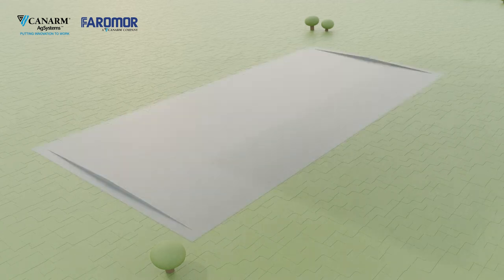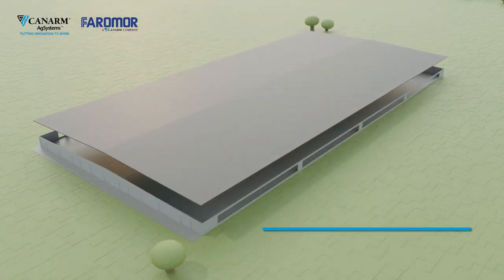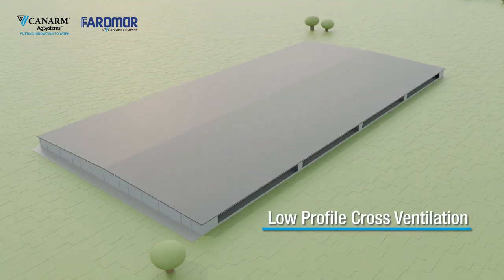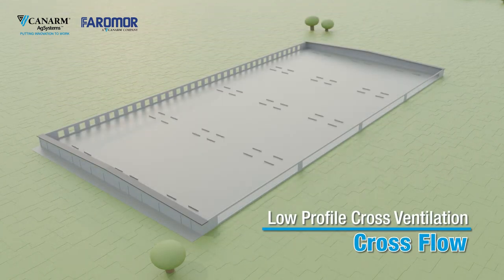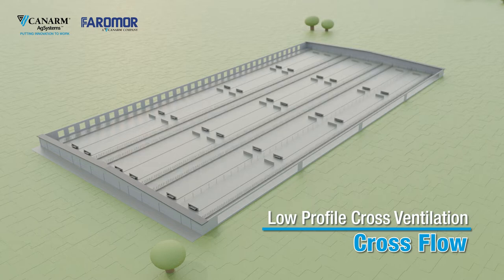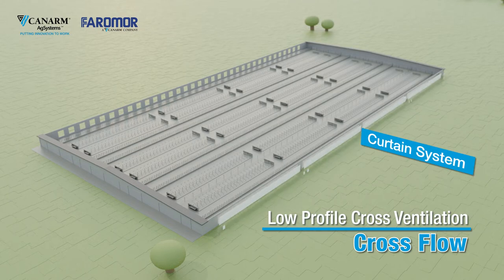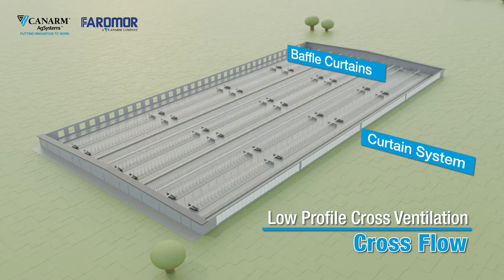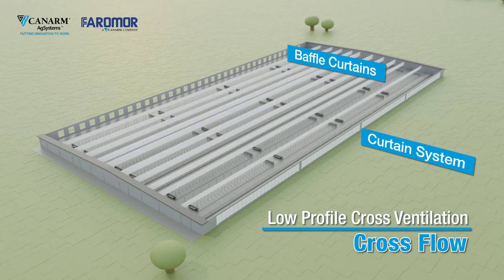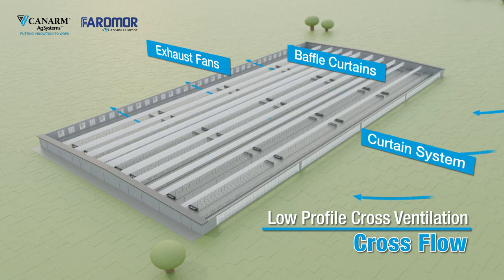A barn layout option to consider for large dairy herds is the low-profile, cross-ventilated free stall barn. Typically 8-16 stall rows wide, a cross-flow barn utilizes a curtain system on one long sidewall as an inlet, baffle curtains within the barn to direct airflow over the cows for maximum cooling, and a continuous bank of large capacity exhaust fans on the opposite sidewall to move the air.